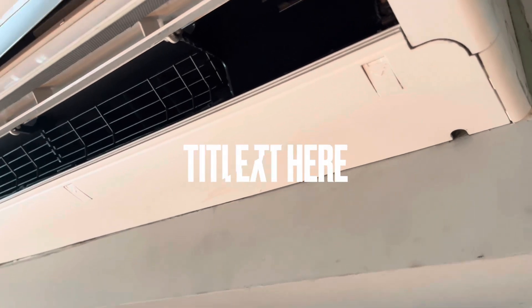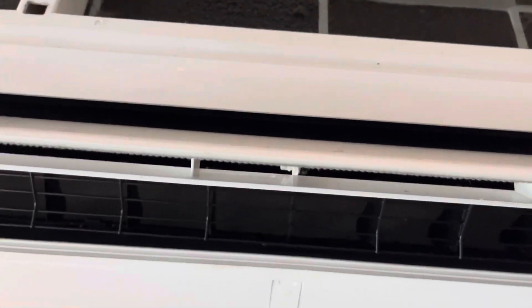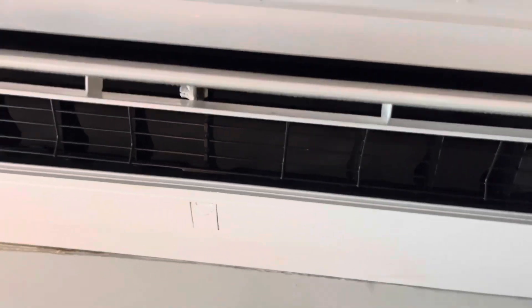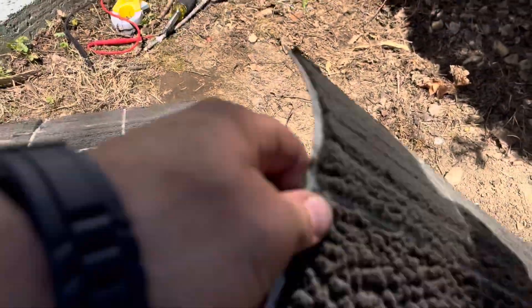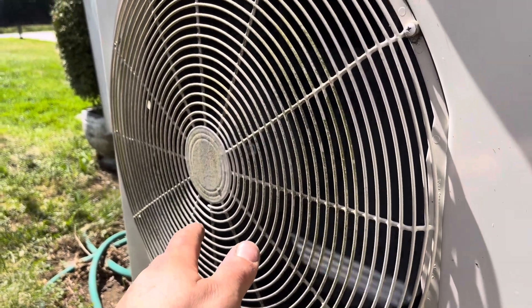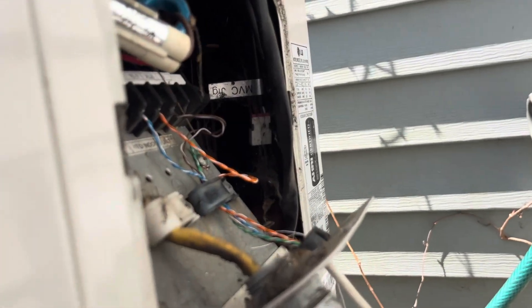How are your filters? Have you cleaned them? No, I haven't really — I use the fireplace most of the time, but I will. Yeah, these need to be cleaned. Because there's thermistors in here and it senses temperature. Do I clean them or buy them? No, you clean them. Can we wash them? They have to be done now. Do you have a hose outside I can use? So this unit, my friend and I changed the head on it about two years ago because it was really dirty — she didn't want to breathe it in from the previous tenants.